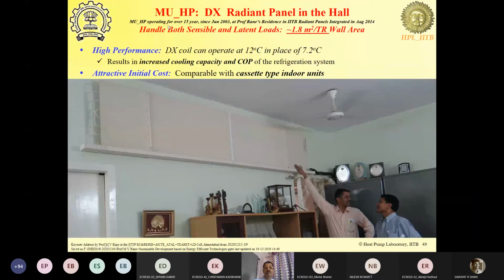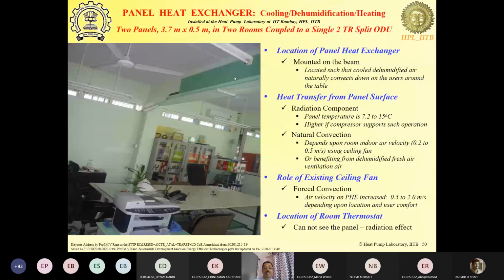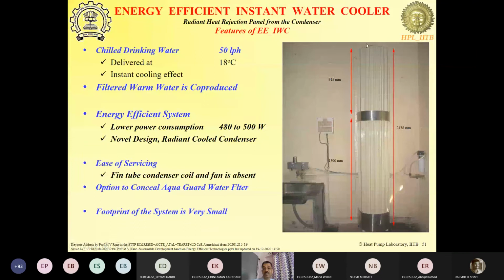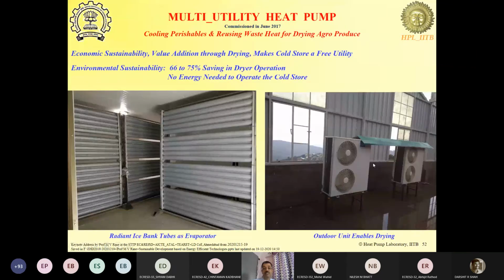The multi-utility heat pump, 4-in-1 multi-utility heat pump, has been operating in my house for the last 15 plus years. In fact, 17 years now. Okay. About 6-7 years ago, we replaced these with these panels because the indoor unit, the conventional indoor unit, after 10 years started making noise. So now we have replaced this with a fanless unit, and we use the ceiling fan to improve the performance. This is a similar unit inside my office area, the radiant condenser for a water cooler. Then I showed you the radiant evaporator in the Nagaland project.